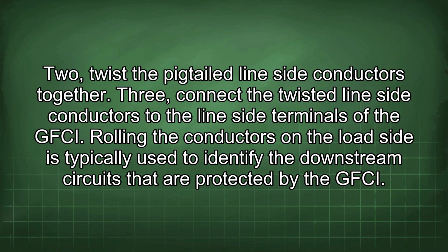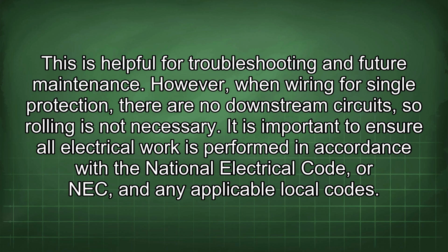Rolling the conductors on the load side is typically used to identify the downstream circuits that are protected by the GFCI. This is helpful for troubleshooting and future maintenance. However, when wiring for single protection, there are no downstream circuits, so rolling is not necessary.